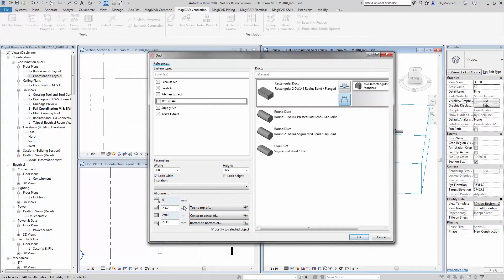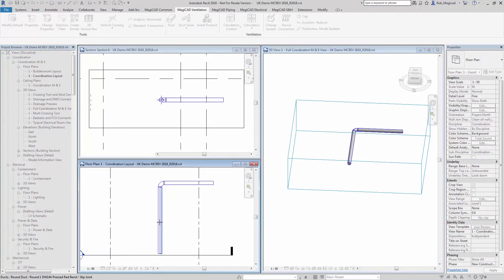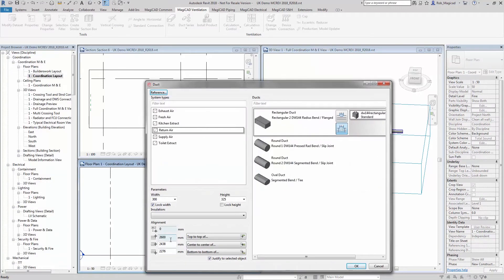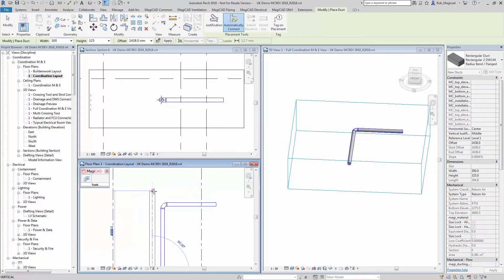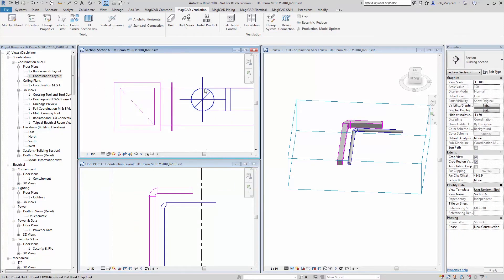What we'll do now is make sure that justify is checked and then we'll click 'top of,' then we'll click the top of the duct which it needs to be justified to — which is this circular one here — and it will read the information from that view and make sure the top of that duct is aligned. Then I'll press OK and draw that rectangular duct in this view, and you'll see on the section view that the top of the duct there is aligned to the top of the duct there.